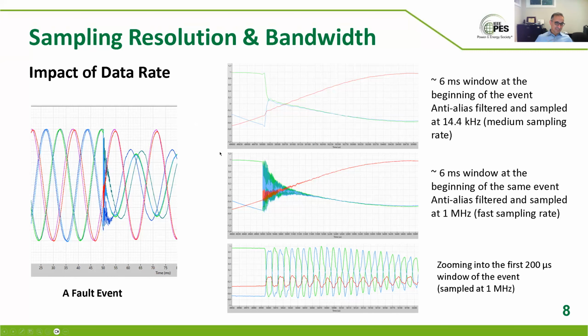And we zoom in on that little time just at the inception of the fault. This is the fault waveform on just one side of the line, the three phases. This is a B to C kind of fault. You can see the voltages come together. This is 6 milliseconds, a bit less than half a cycle, and it's sampled at 14.4 kilohertz. This is the higher IEC rate so that you can do power quality metering. And that's what the waveform looks like.